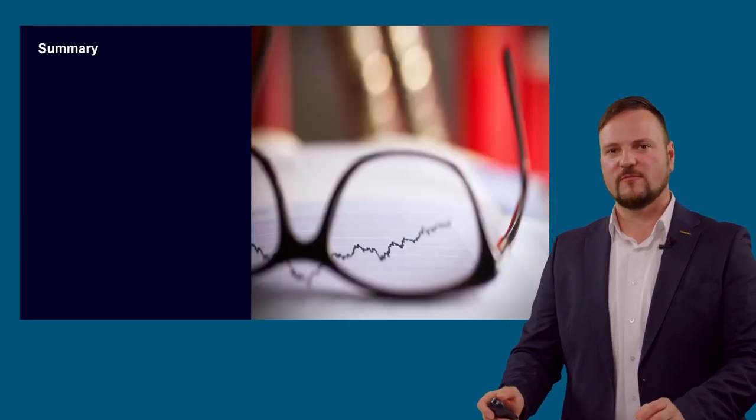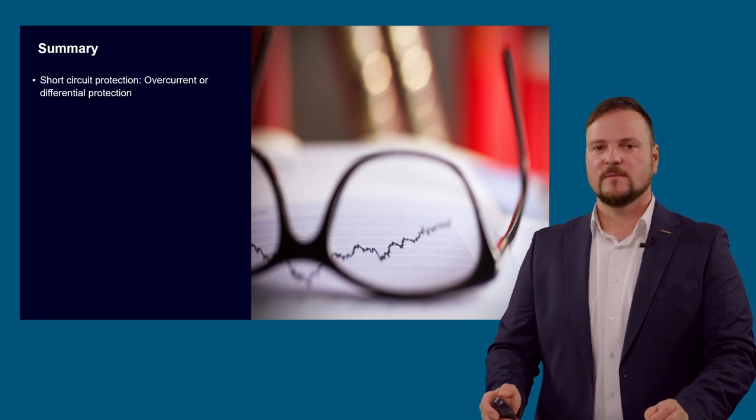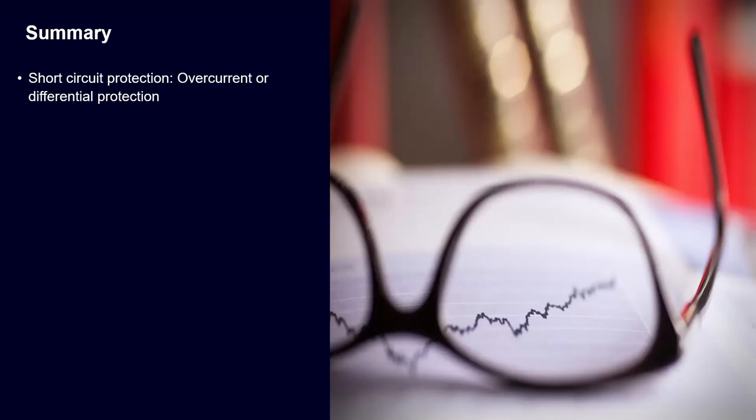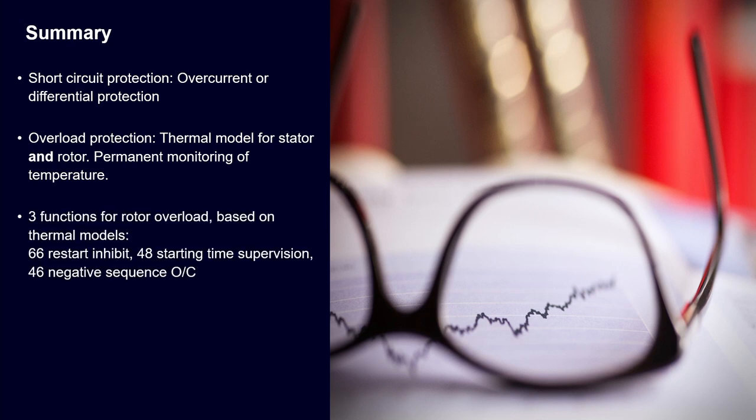So come we to the summary of my presentation. This was a brief overview of some motor protection functions in our SIPROTEC 5 device. We talked about the overcurrent and differential protection as short circuit protection. We came across the stator overload function and its thermal model. And we discussed that SIPROTEC 5 devices offer an additional and sophisticated thermal model for the rotor, which is the basis for the restart inhibit function. Using this model and the function allows much more flexible operation of the motor, monitoring at the same time permanently the rotor temperature. We saw how to set the starting time supervision based on the locked rotor times. And finally, I gave you an insight into the unbalanced load protection, which is based on the thermal model for negative sequence current.